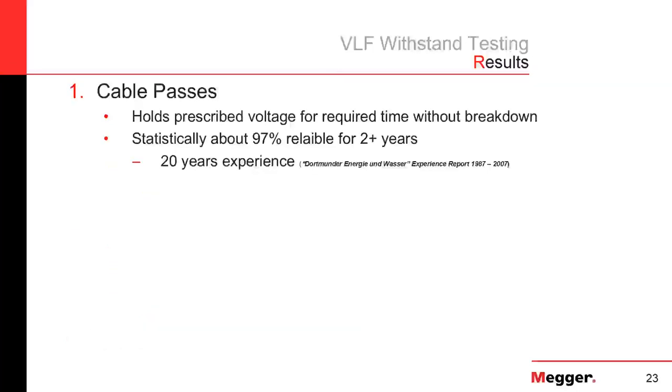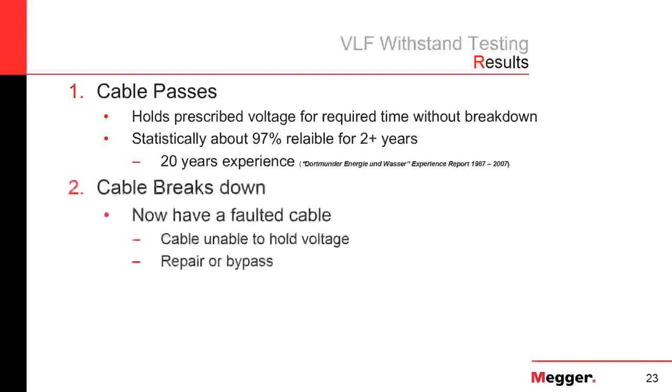So the results then: the cable can pass the test. In that case, it's held the prescribed voltage for the required time and it has not broken down. Statistically, we find that that's about 97% reliable for the next two or more years. That's based on field results.